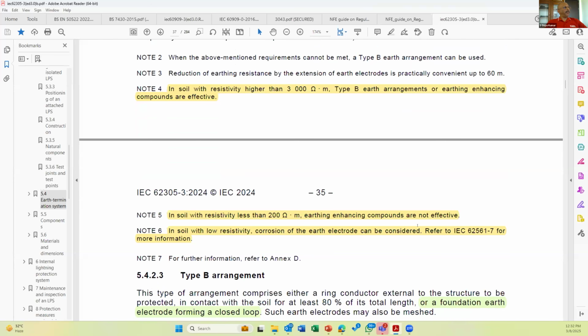With low soil resistivity, corrosion of the earth electrode can be considered from the standard IEC 62561 part 7, which is also an Indian standard now. So basically, if you put this chemical in the earth electrode, you are actually increasing the corrosion of your earth electrode. So if you have soil resistivity more than 3000 ohm meter, probably you can think of chemical. Otherwise, don't use it.